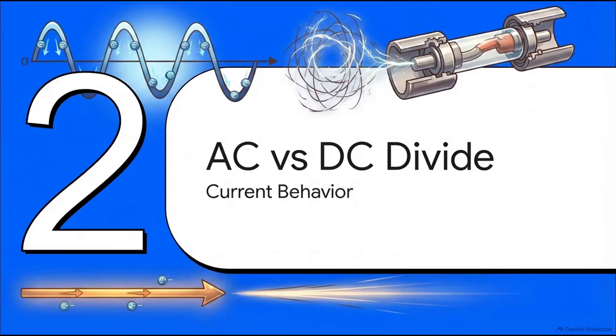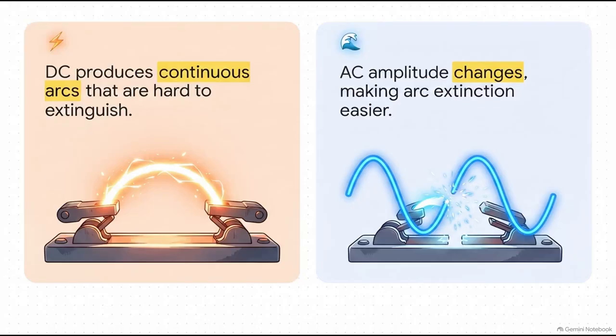But before we can get into the mechanical designs, we have to talk about how the current itself behaves. Chapter 2, the AC versus DC divide. So the crucial thing to understand is that not all electricity acts the same way when you suddenly break a circuit. When a DC fuse opens a circuit during an overcurrent event, boom, an electrical arc is produced. And because direct current is continuous, meaning there's literally no point where the current drops to zero, that arc is incredibly stubborn and hard to extinguish. To fight this DC arcing, engineers actually have to place the electrodes at a much greater distance apart, which is why DC fuses are physically larger.